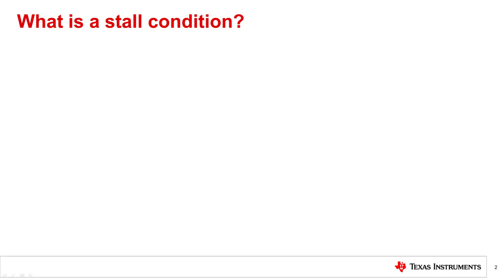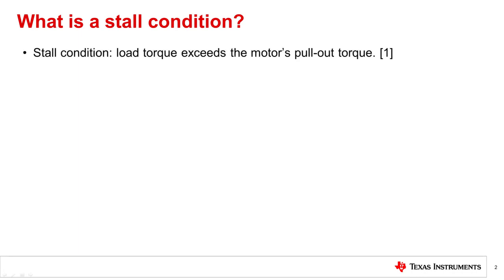Let's begin by discussing what stall is and what the main causes of stall are in a motor system. A stall condition occurs when the load torque on a motor exceeds the motor's pullout torque. The pullout torque is the maximum torque that the motor can produce at a given speed before the rotor becomes out of sync with the magnetic field. When the rotor becomes out of sync with the magnetic field, the motor will stall.